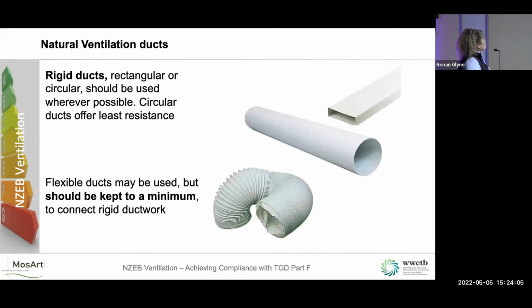So rigid ducts, rectangle or circular, should be used where possible. Circular ducts often offer the least resistance. Okay, so the air flows better through the round duct than it does through the square duct. Again, if you can cut down the amount your fan has to run, the more the better. Flexible ducts should be kept to a minimum and only to connect to rigid ductwork. So we're going again for the rigid ducting and we're leaving the flexible ducting off.